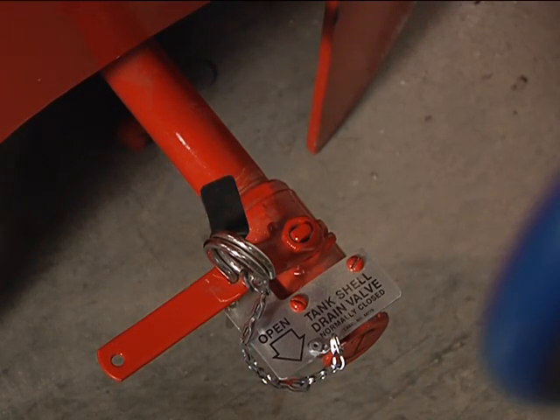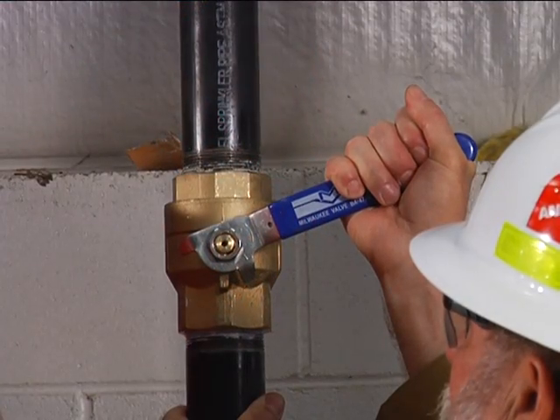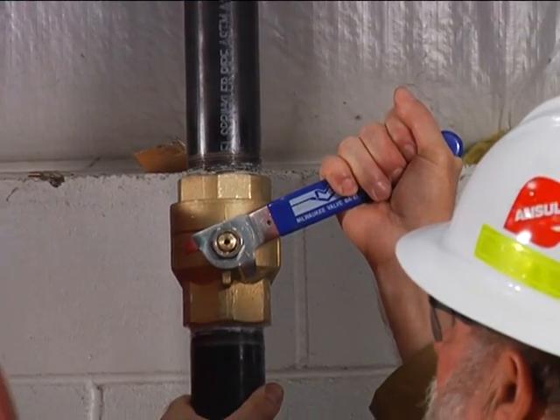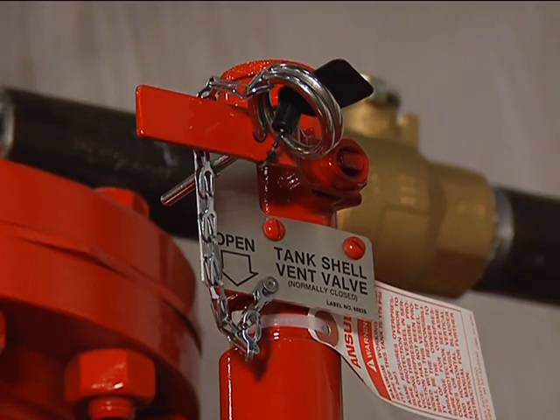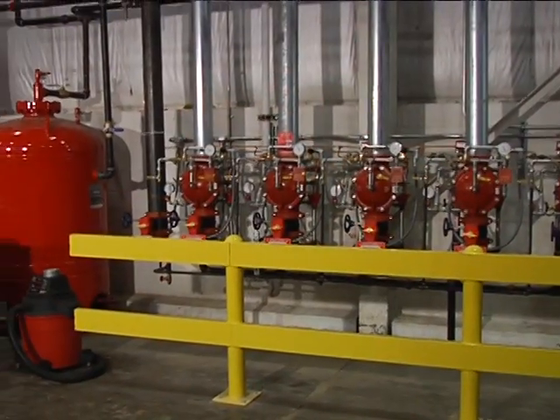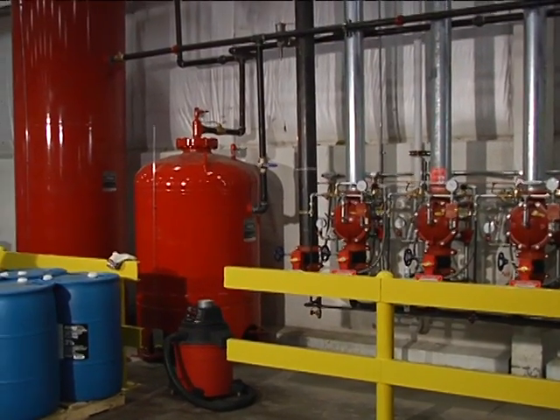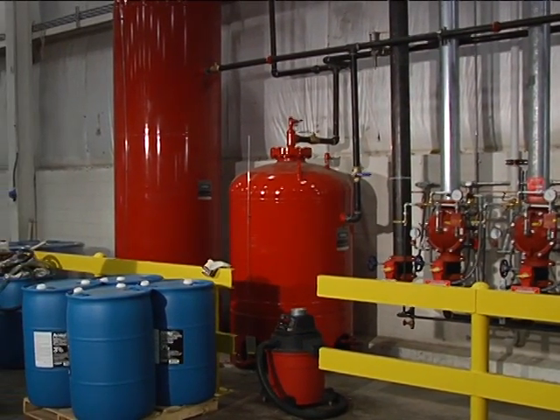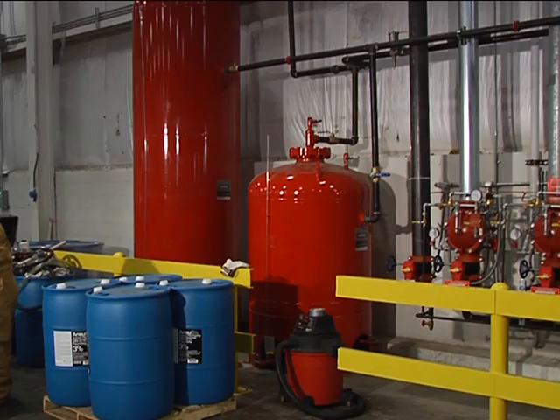Close the tank shell drain valve and slowly open the water inlet valve to vent the air between the bladder and the tank shell. Finally, close the tank shell vent valve. You've now successfully used the sight gauge method to measure the foam concentrate within your Ansul bladder tank.